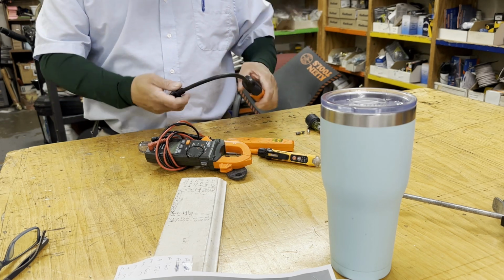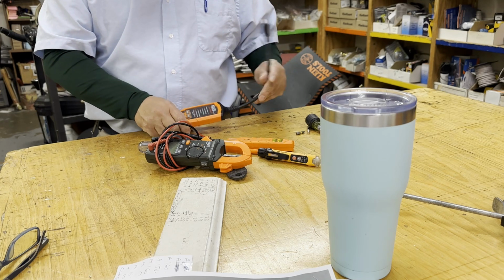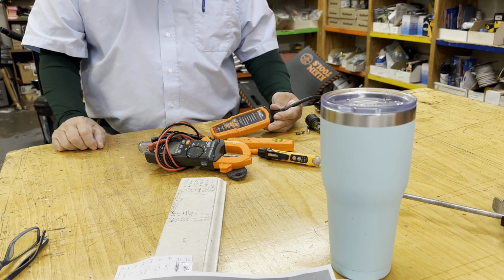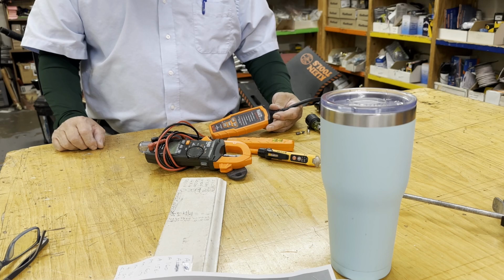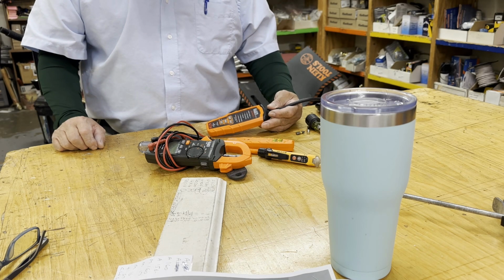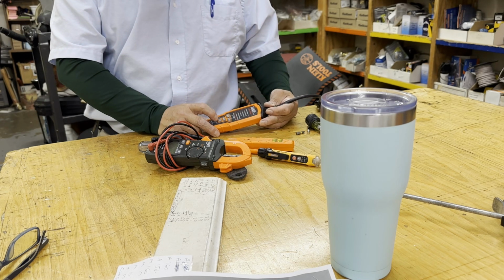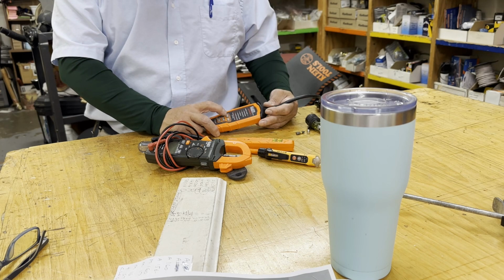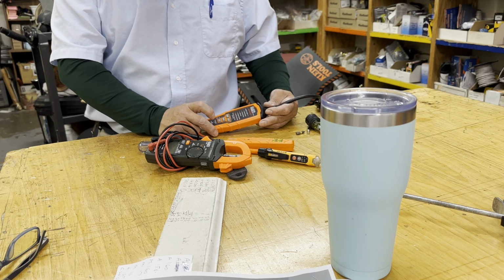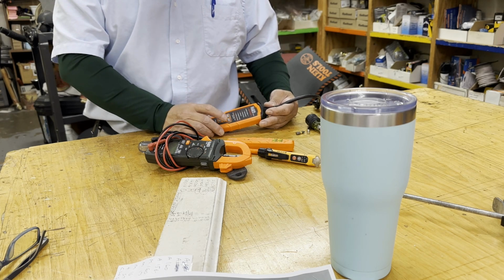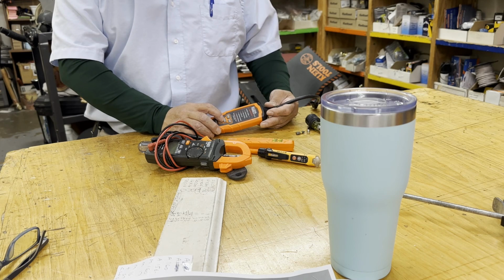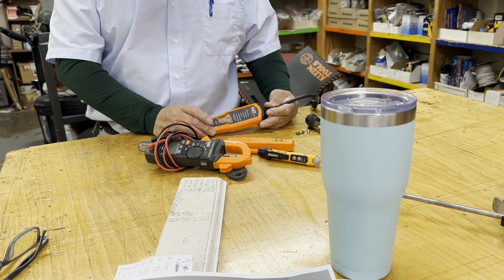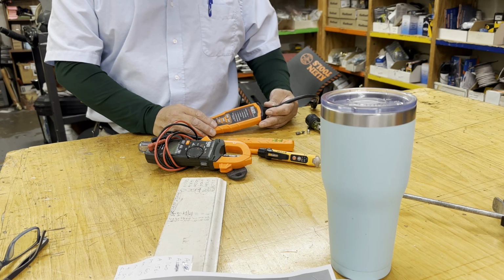Have a video on this one. This guy's not no joke. He can get to breakers that are arc fault, whether they be Cutler Hammer, GE, stuff like that. They can sometimes do Square D. The more versatile thing here is it has the regular arc fault, the GFCI, and it has a 30 milliamp, which is a little more powerful. If you have trouble with these two, you can press the 30 milliamp and it should help you trip that breaker. Really, really big deal. You guys got to see that video.